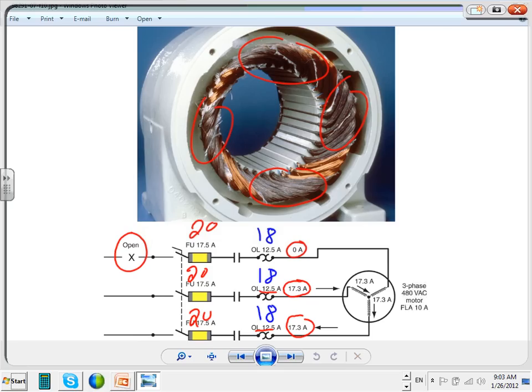Now, when would the fuse wake up? Very good point. Well, why do I have a fuse? Here's when you have a fuse. Suppose that this phase here shorted to the ground, right? Could happen. Take this phase, shorted to the ground. This is still on and shorted to the ground. In a case like this, you're going to have a huge amount of current. Huge. You're not going to have 17.5. You're going to have close to 1,000, 2,000 amps of short circuit.